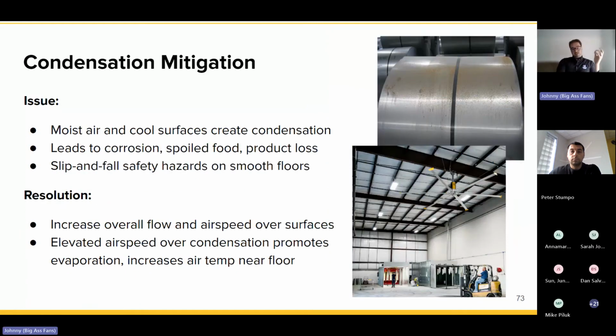Another big piece is condensation. Again, not thinking about people here, thinking about product. We've seen cases where they were losing hundreds of thousands of dollars a year just in corrosion costs. If you can raise the temperature of things like steel coils or even a concrete slab, you can reduce that temperature delta, which means when the warm air kicks on and hits a cold surface, there's less of that dew point effect happening. So we can raise the temperature of the ground and reduce that condensation effect. And if condensation does occur, you're using fans to wick away that moisture, so it's evaporating much quicker.